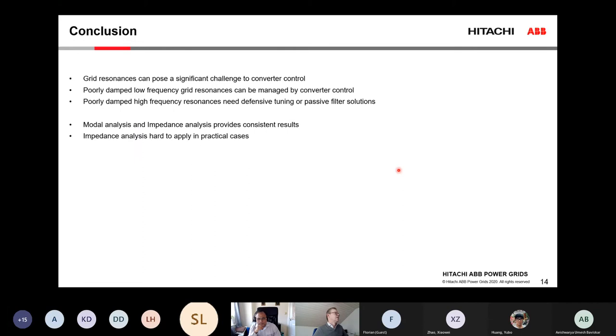To conclude this very brief overview, when we have resonances in the grid, this can give us quite big challenges for the converter control. We need to consider them when we design the converter. But if you know about these resonances, you can quite often manage at least the low frequency resonances quite well with control. Resonances that come high up in frequency, in frequency ranges mapping to the time delay of the converters, may be more tricky to handle with control. So we may actually need to use a defensive tuning and look at passive filter solutions to manage that.